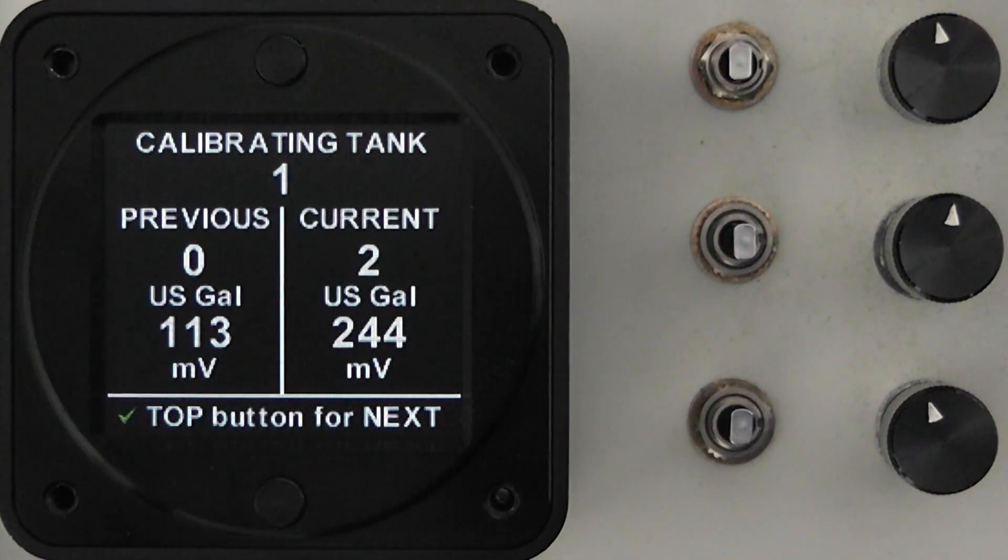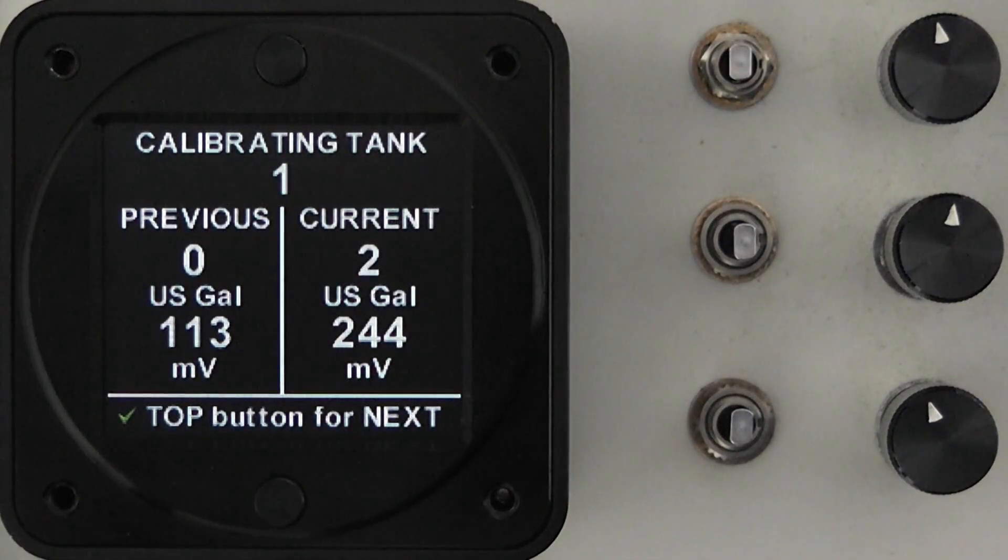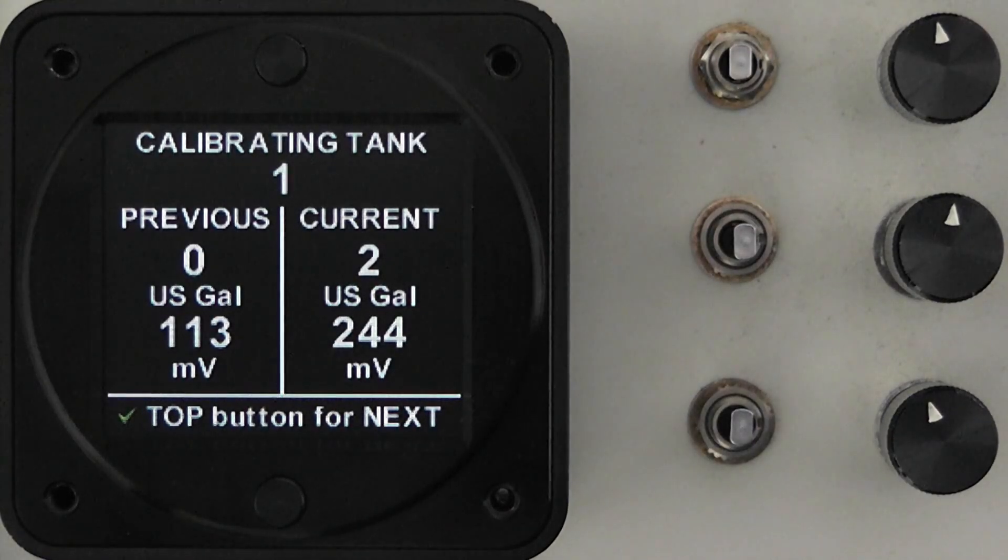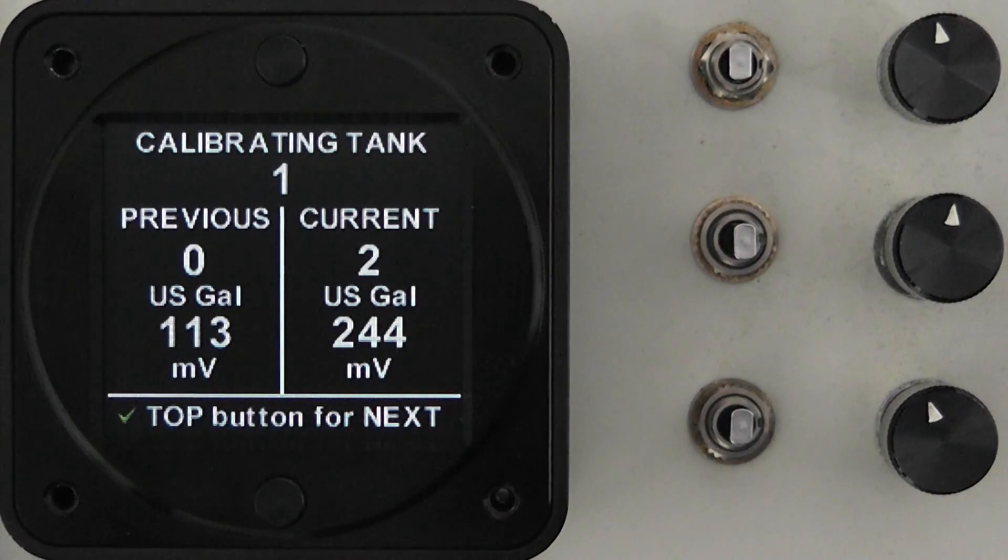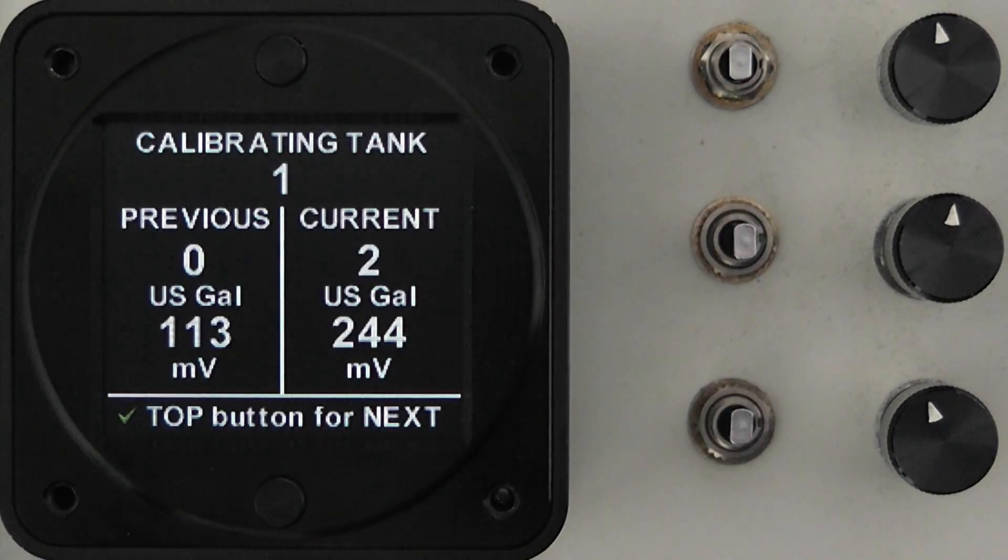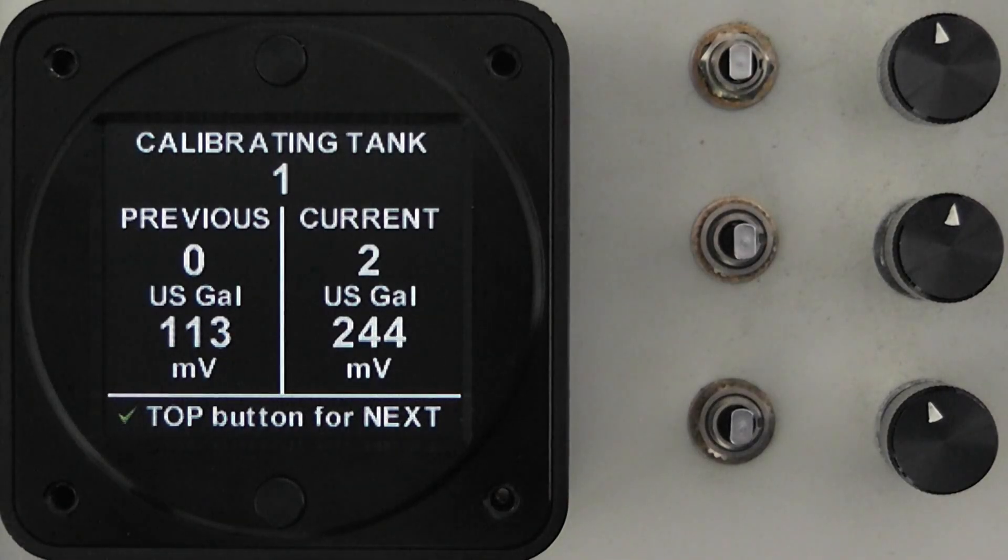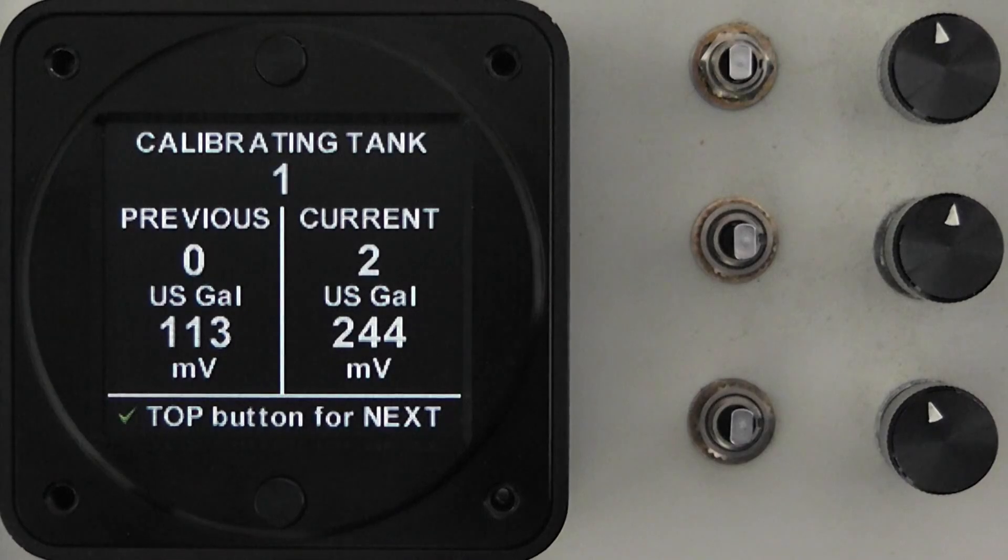You'll now see that you've got the previous reading which was the 113 millivolts and the next reading where the two gallon point, now because you now have two gallons of fuel in the tank, is 244 millivolts. Again you write this number down in your calibration sheet and the instruction tells you at the bottom top button for the next. You'll also see next to it is a green tick mark.